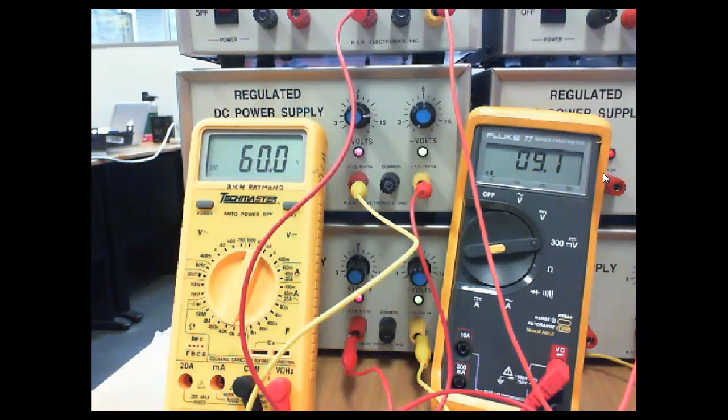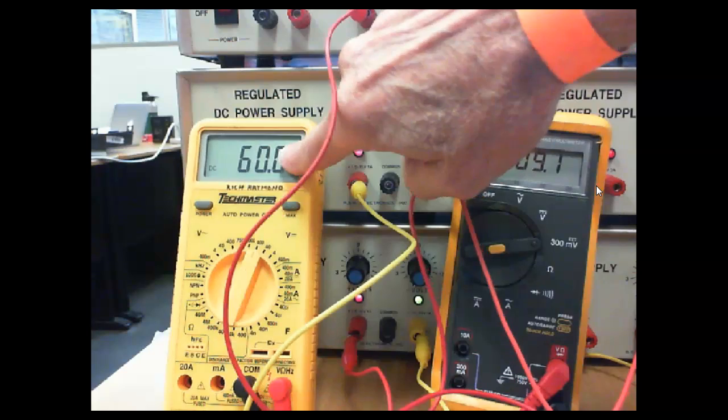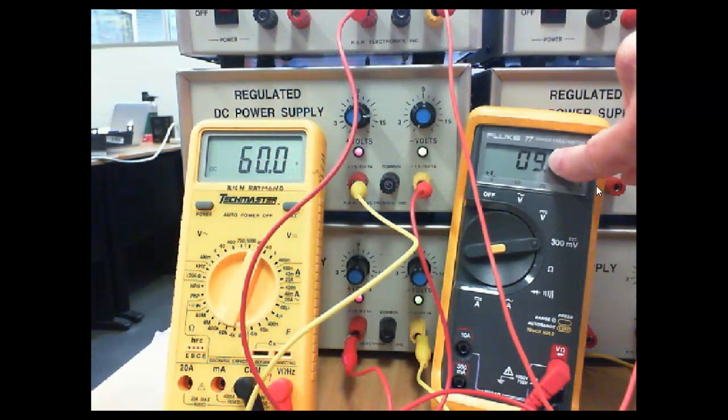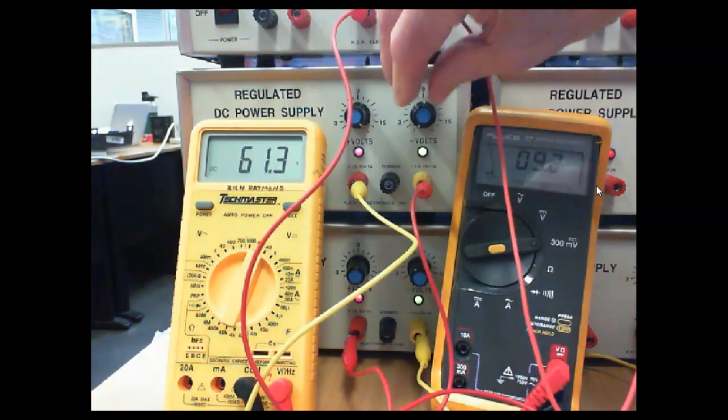Are we okay? Still moving slowly. What we're going to start looking for is this major division to change as fast as this division right here is changing. That indicates breakover. That's exactly right. Whatever voltage is on here when this digit starts advancing real fast, that'll be our highest measurement. Break it over now.